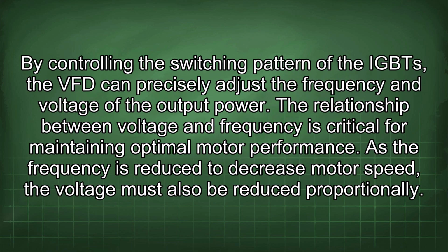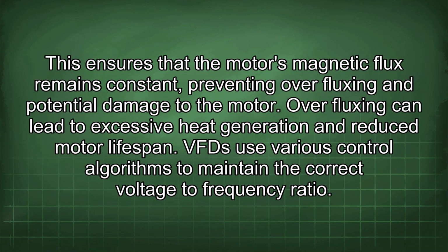By controlling the switching pattern of the IGBTs, the VFD can precisely adjust the frequency and voltage of the output power. The relationship between voltage and frequency is critical for maintaining optimal motor performance. As the frequency is reduced to decrease motor speed, the voltage must also be reduced proportionally. This ensures that the motor's magnetic flux remains constant, preventing overfluxing and potential damage to the motor. Overfluxing can lead to excessive heat generation and reduce motor lifespan.